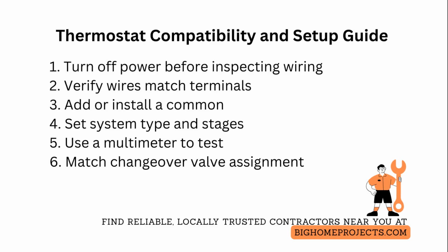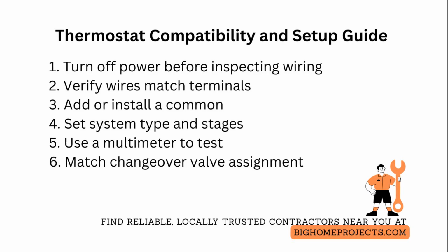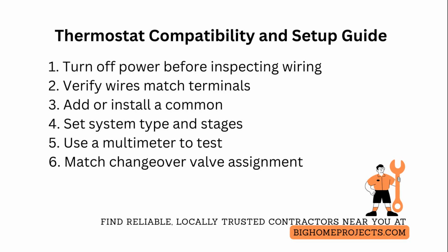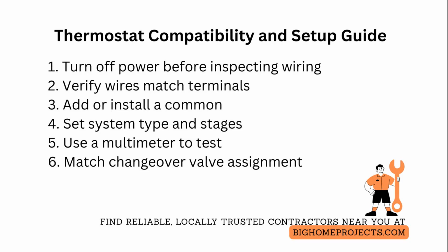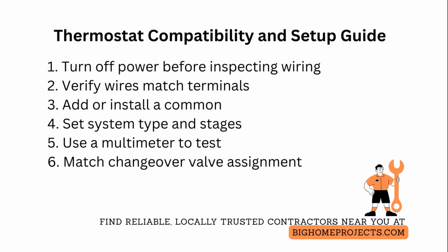If you experience persistent fan or short cycling issues, enable configured cycle rate limits and minimum runtimes in the thermostat's installer options to protect equipment and confirm the fan control setting, auto versus on, matches your system's fan relay wiring. Keep the unit's firmware up to date where applicable. Download updates from the manufacturer using the model number and follow their upgrade steps to restore advanced scheduling and remote diagnostics. Finally, document every change you make with photos and notes so a technician can pick up where you left off if professional help is needed.